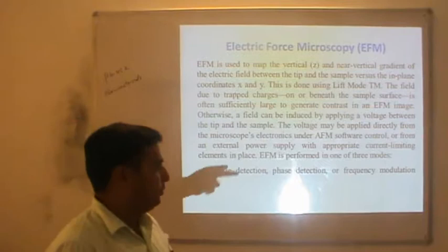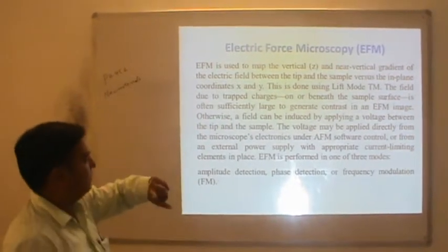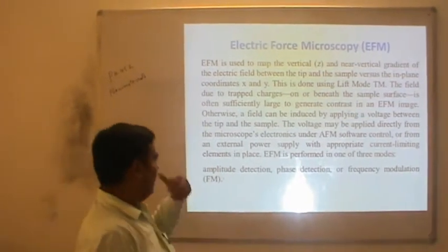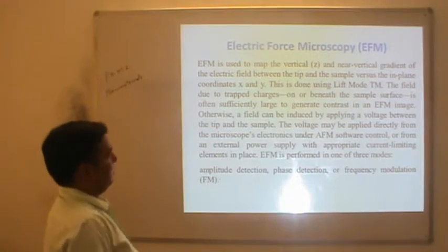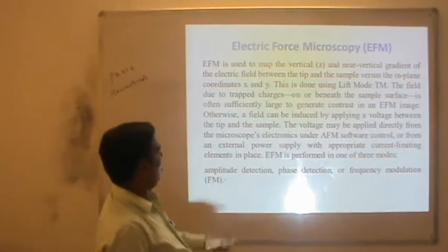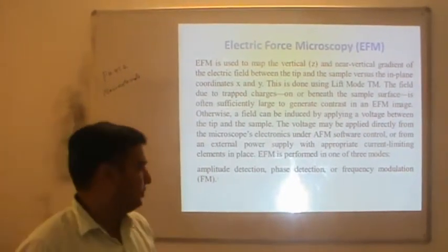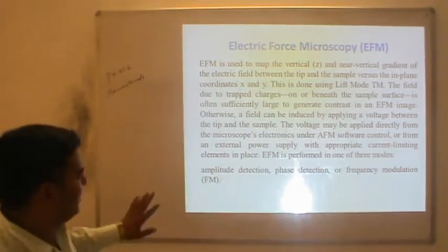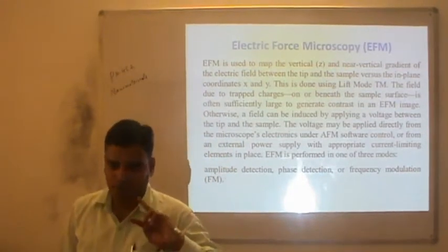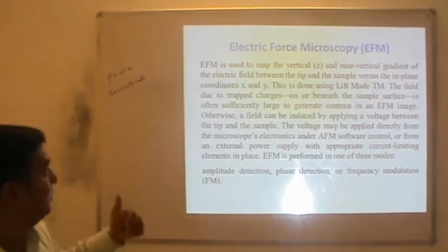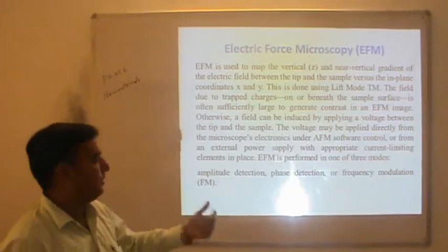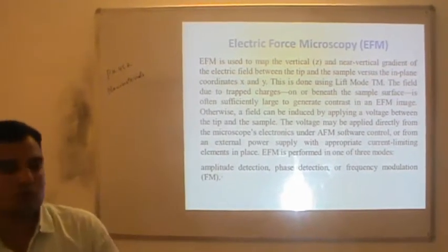If there is no sufficient electric field generated between the tip and sample, a voltage can be applied externally — either directly from the microscopy software or from an external power supply with an appropriate current-limiting element. By measuring the electrostatic force between tip and sample, we can form an image of the sample, including topographic information.